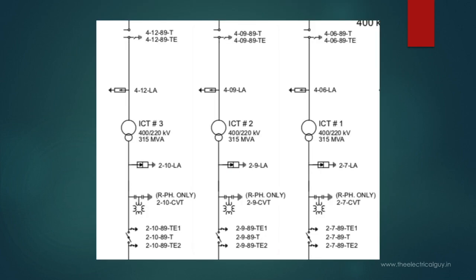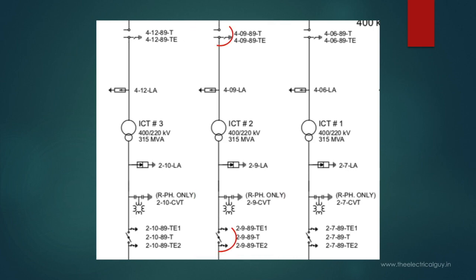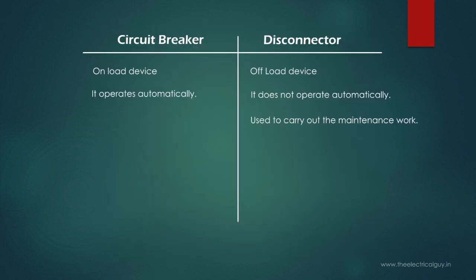Similarly, if I want to carry out the maintenance of this section, I will simply open these two disconnectors. This symbol indicates a double break type disconnector with two earth switches. Whereas the breaker is used to protect the system from fault current. It is not used to carry out any kind of maintenance activity.